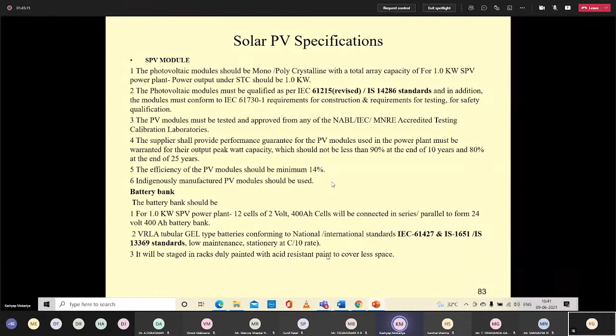When I prefer cost competitiveness according to my condition, at that time I define VRLA tubular gel type batteries of the standards. So again I have to deal with standards. I have to see what IEC 61427 is, what IS 1651 is, what the IS 13369 standard is, and stationary at a C/10 rate specifically for this solar PV application. It will be staged in racks duly painted with acid resistant paint to cover less space.